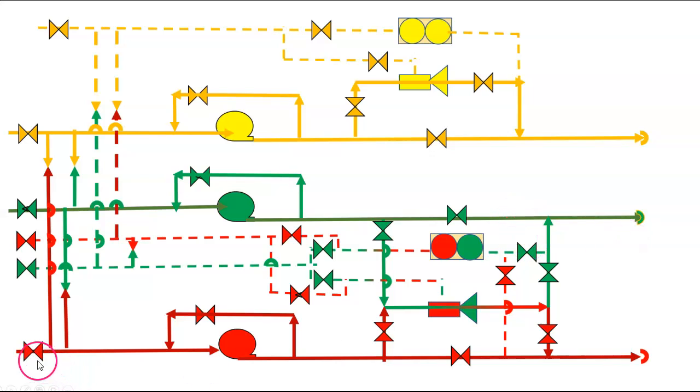Okay, so I can pump that out. Can I do it with the red? Yep. Okay, I'm going to open this up with the red. I'm going to close the recirc line. I'm going to close the eductor feed, the eductor discharge, and the stripper discharge. Open up this. I only have to open up 2 valves. 1, 2. Start up the pump, and away I go. All right. The next test.